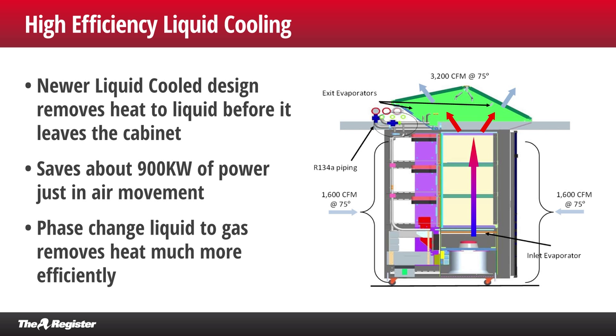It's just a very small pump rather than a big compressor and expansion valves. The real advantage is that if you had an expansion valve and compressor, you'd get condensation on the pipes and risk water dripping into the electronics. With this system, the physics prevent any condensation — nothing ever drops below the dew point — so you never get condensation and don't have to worry about water.